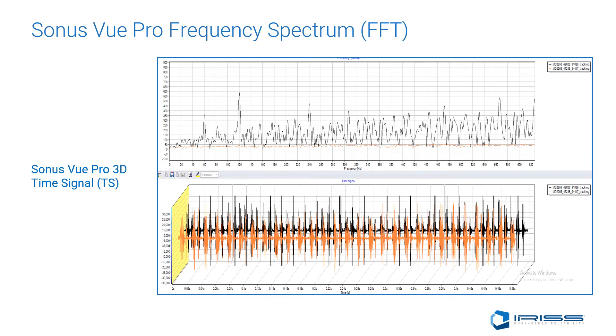Only when both sound waves are run through the Sonus Vue Pro software can the inspector verify they have achieved the critical angle of electrical events. It is very important to walk around and listen while moving to find the critical angle of the ultrasound anomalies. The key is using decibels only as an indication of increased signal strength — decibels should never be used for gauging severity of electrical anomalies.